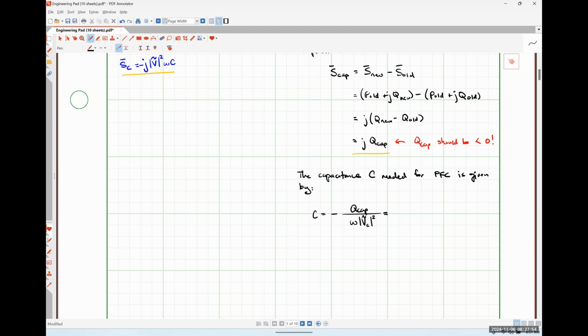That relationship looks like: P old times the tangent of theta old minus the tangent of theta new, divided by omega times the magnitude of the voltage drop across the capacitor squared. So if I know my old power factor angle and my target power factor angle, I only need the average power, which is constant for both, my angular frequency of excitation, and the voltage drop across the capacitor.